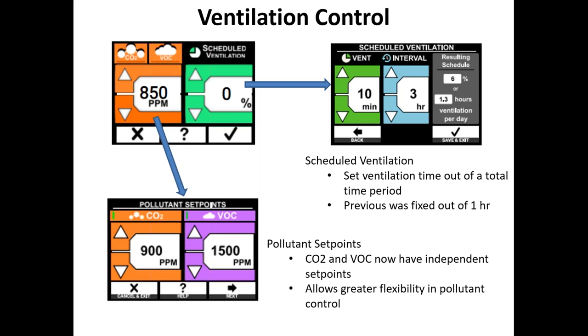So generally, you may set the CO2 a bit lower than VOCs. It's a total VOC reading, so it's not specifically measuring ones that are necessarily bad. And so this just gives you more flexibility in a space where you may have higher VOC levels. Previously, you could still disable the VOC from triggering ventilation, but this just lets you instead set a higher triggering set point if you're okay with slightly elevated VOC levels.